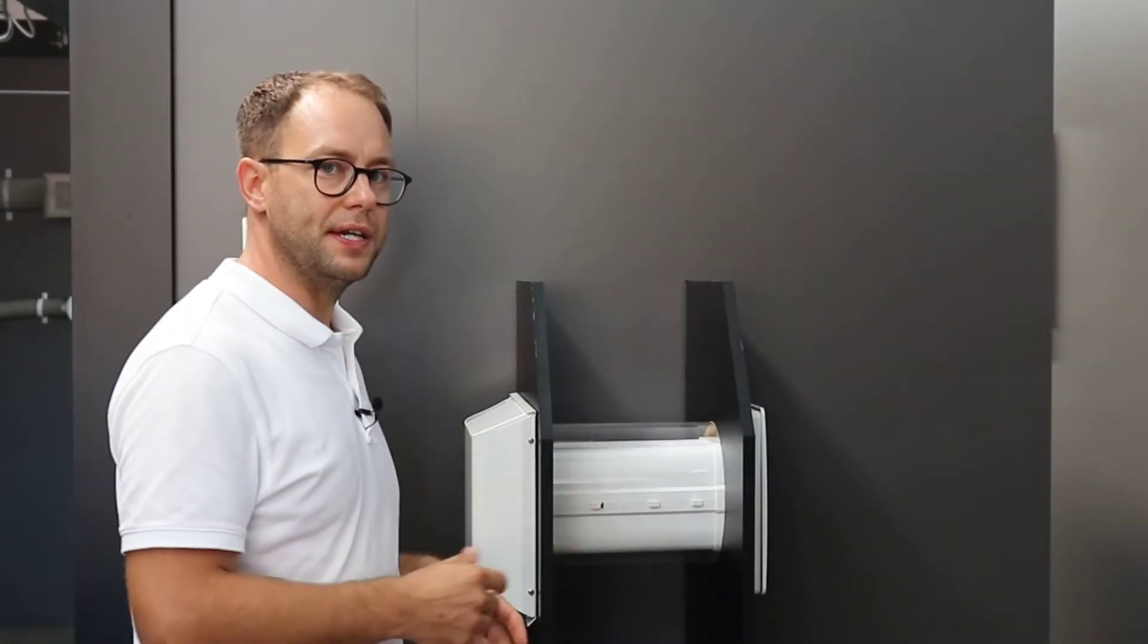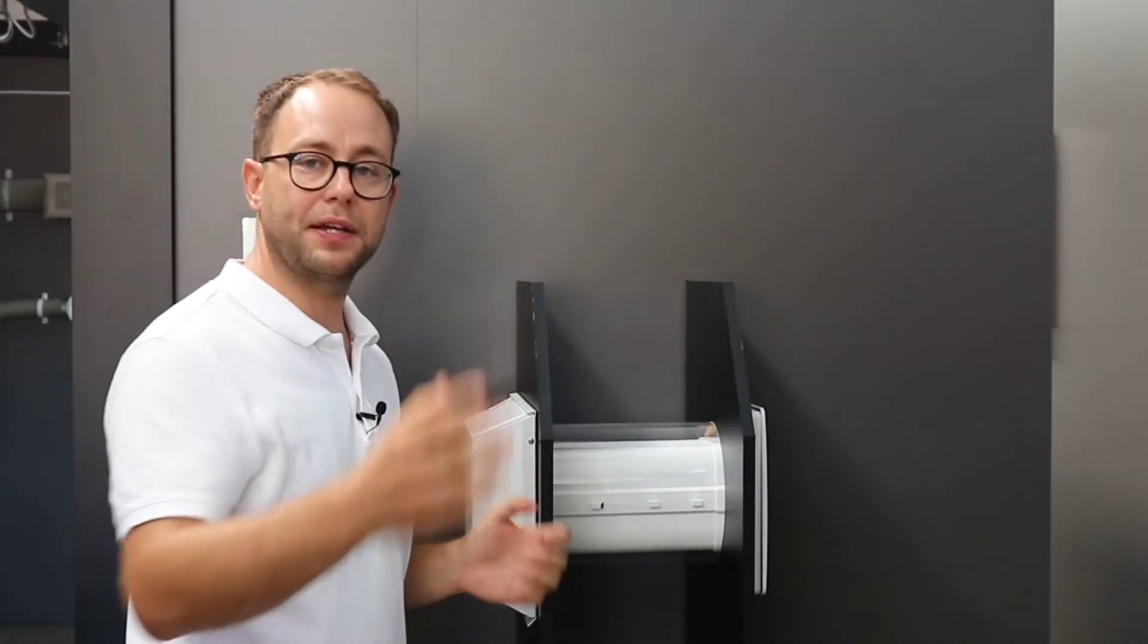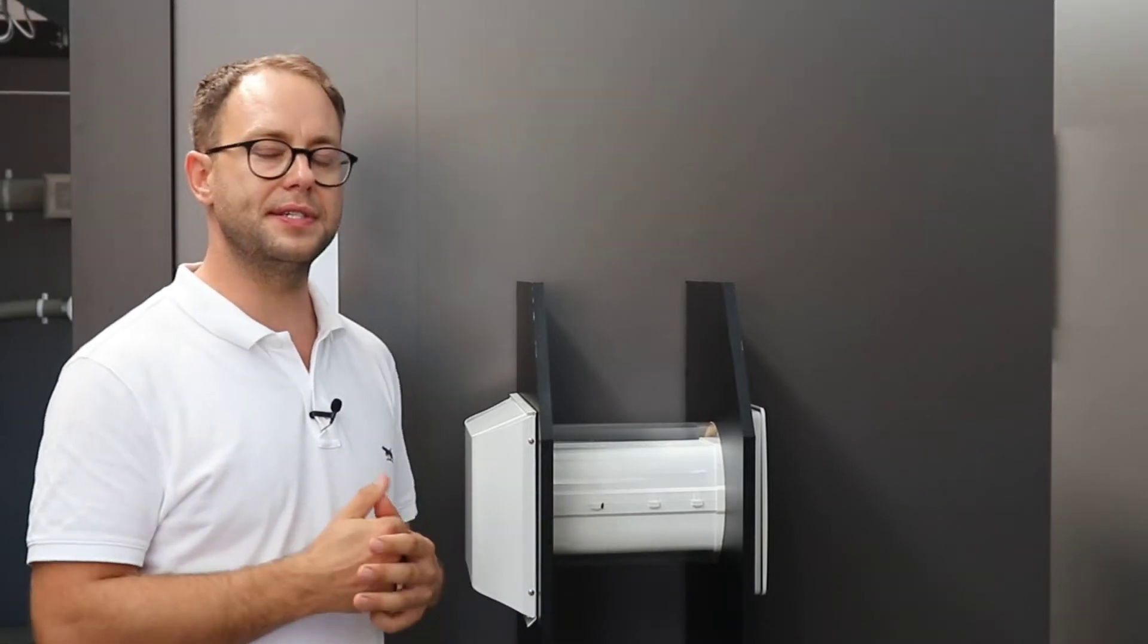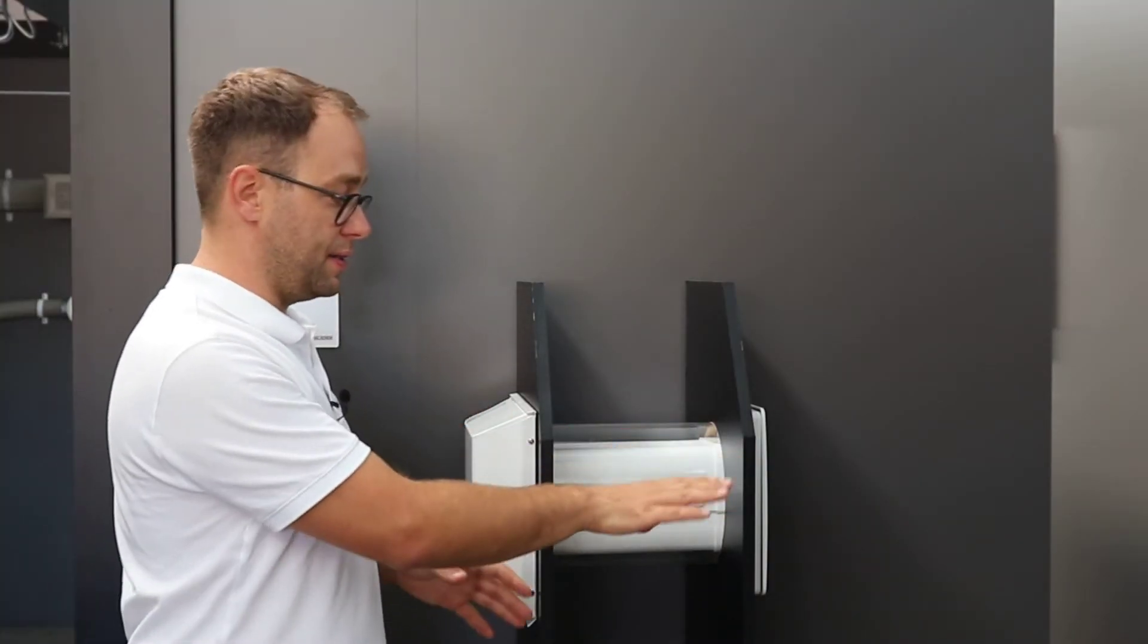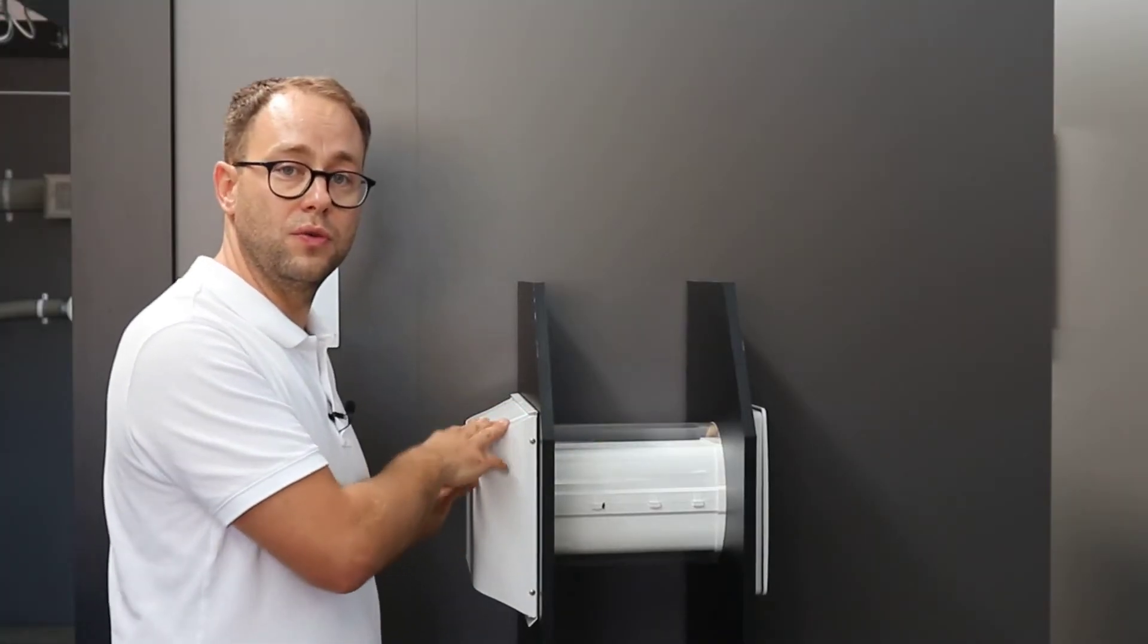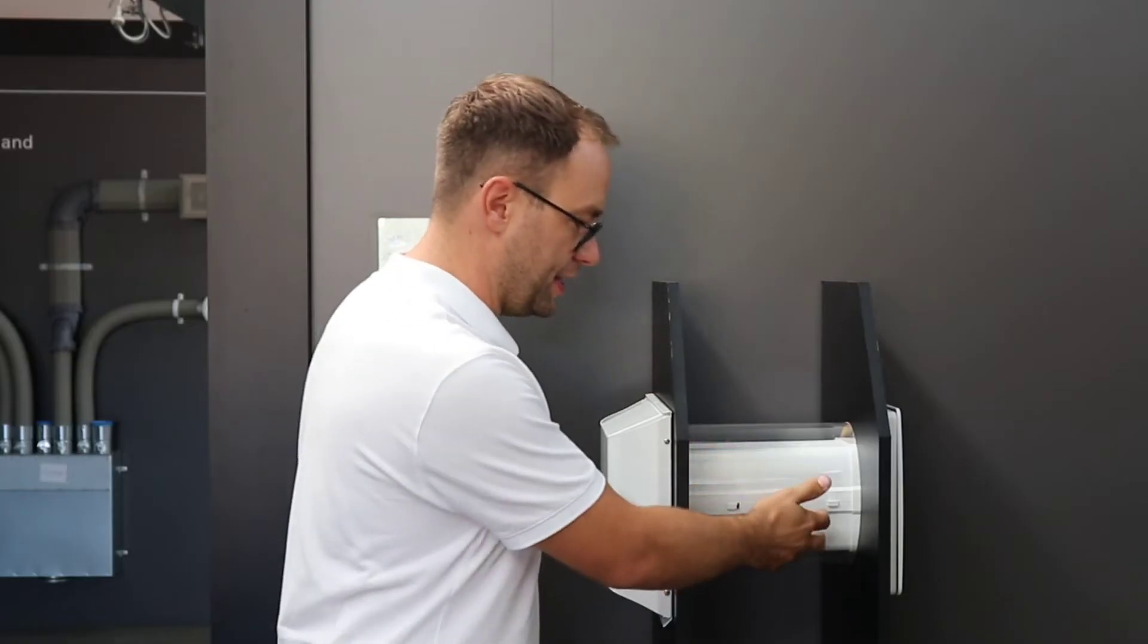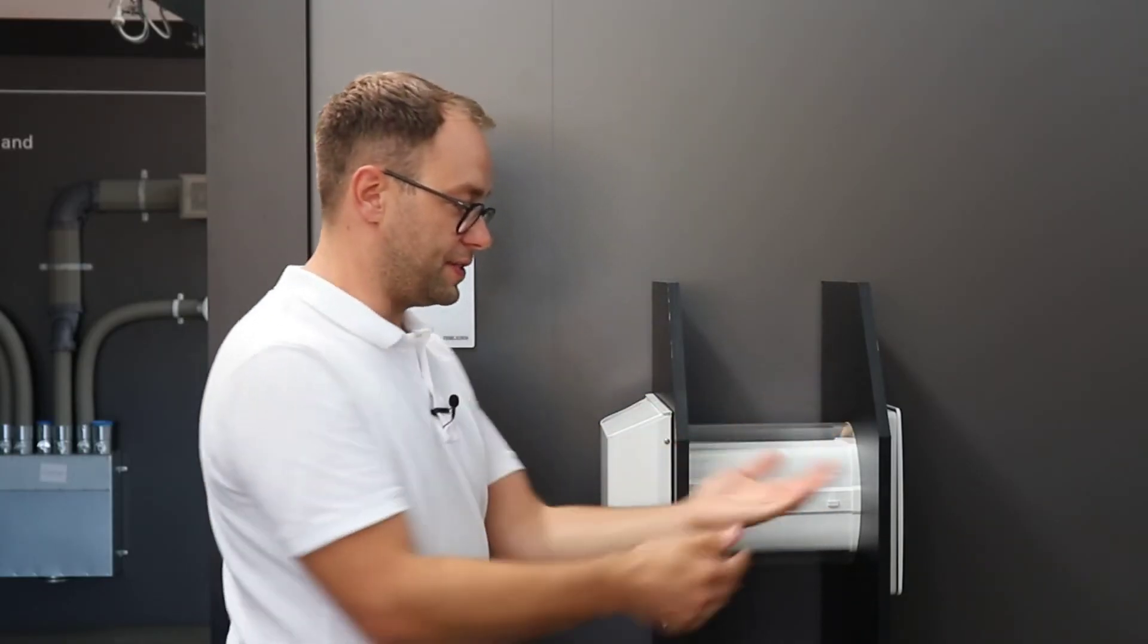A couple of mistakes people make: they don't allow for the cabling. Each unit needs a cable back to a central controller - only a two core cable, low voltage DC, not a headache. But make sure you have that in place. The unit also has to be slightly tilted toward the external louver so any condensation will naturally drain out.